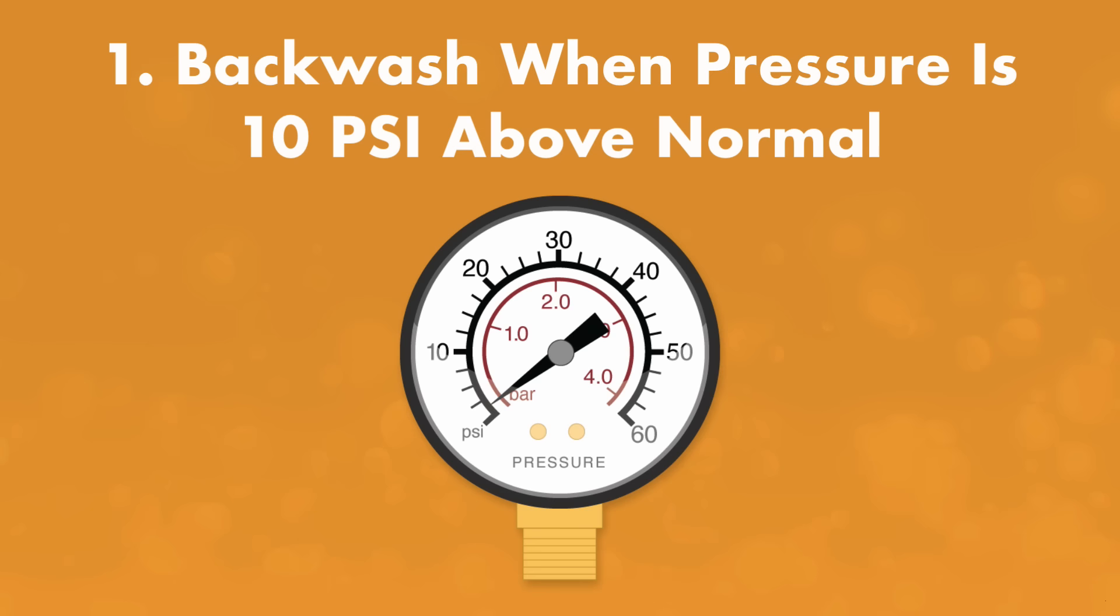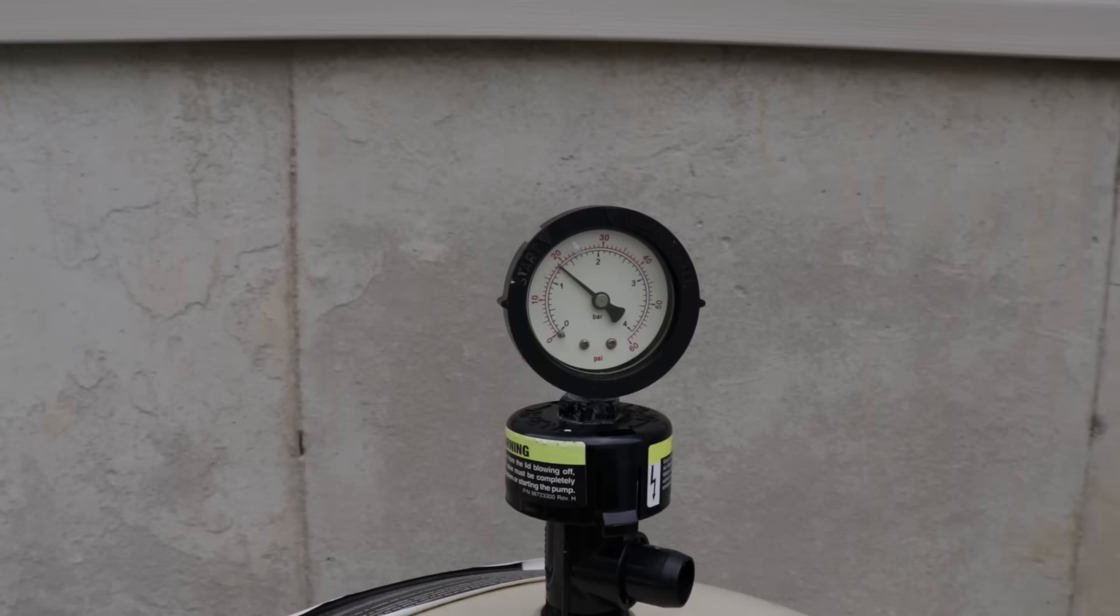Rule number one, backwash when your pressure reads 10 psi above normal. If your pressure gauge is 10 psi or pounds per square inch over your normal operating pressure, it's time to backwash. A high pressure reading means that your filter has accumulated enough dirt and debris to prevent water from flowing freely through it.